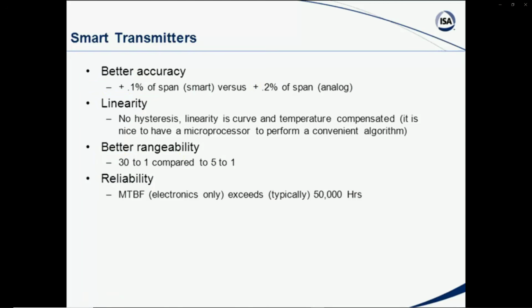So that's very important, and it gives much more varied results with our transmitters, making them much more flexible, much more usable. And then the reliability has gotten better each year. Really, the mean time between failure, for example, on electronics exceeds 50,000 hours or maybe even more than that. So the reliability is extremely high. That helps out our maintenance. It also helps out in many cases our safety systems that we're concerned with, because we just have more reliable devices that give us better results.